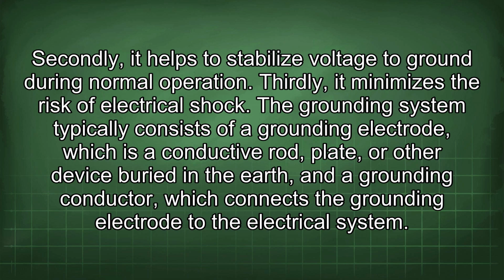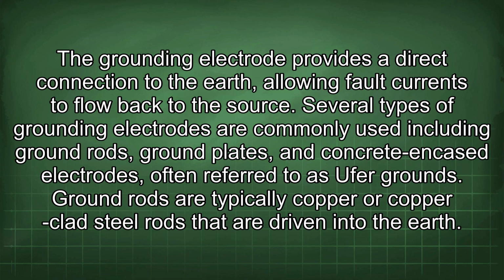The grounding system typically consists of a grounding electrode, which is a conductive rod, plate, or other device buried in the earth, and a grounding conductor, which connects the grounding electrode to the electrical system. The grounding electrode provides a direct connection to the earth, allowing fault currents to flow back to the source.